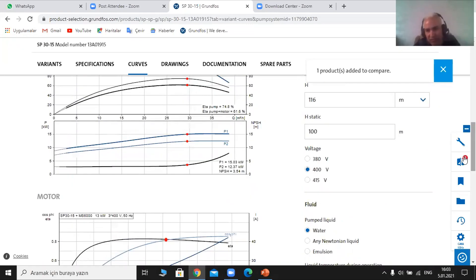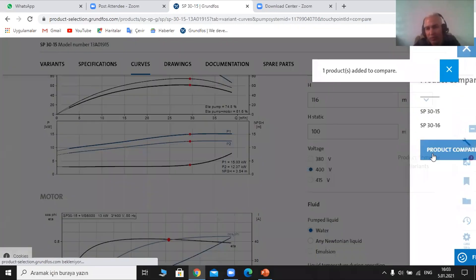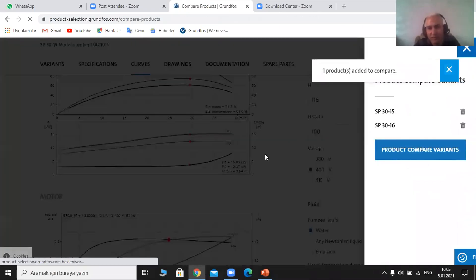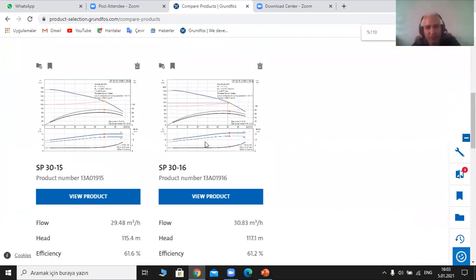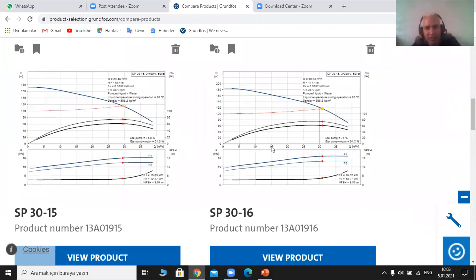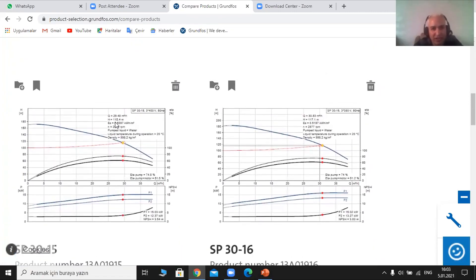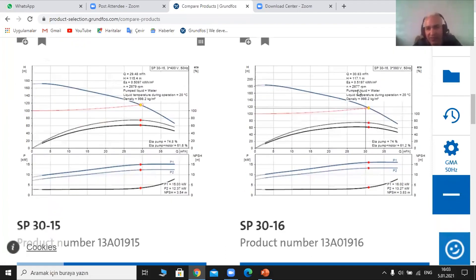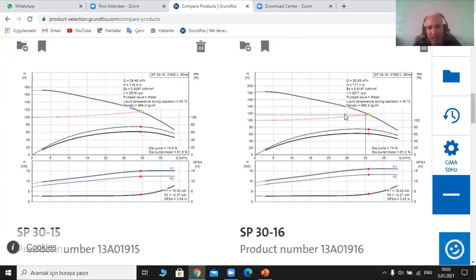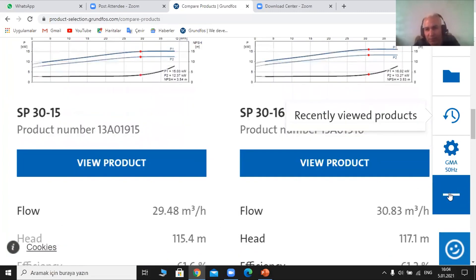If we went to efficiency, maybe one is more efficient. Let's go to 'comparison' and it shows how it compares between the variables. Here I can see the two pumps I would like to compare. For pump 15, the flow is 29.5, while pump 16 has a flow of 30.83. Going down, can you see the flow rate: 29.5 versus 30.8? The head: 115.4 versus 117.1. The total efficiency for the first one is 61.6%, while the other is 61.2%.